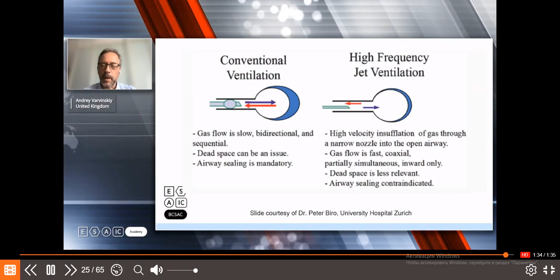The jet ventilation is different. It's high velocity insufflation of gas through a very narrow nozzle into the open airway. So gas flows fast, it's coaxial, it's partially simultaneous, and it's only going in. Then dead space is less relevant, and you cannot seal the airway because, as I said, you need passive expiration for what you have delivered to be exhaled. So it can only be possible in a non-obstructed or at least partially open airway. There has to be a lumen for the volume that you have delivered through the jet ventilator to be exhaled passively, and there has to be enough time for that volume to be exhaled. And quite often, using this method, the volumes are small.